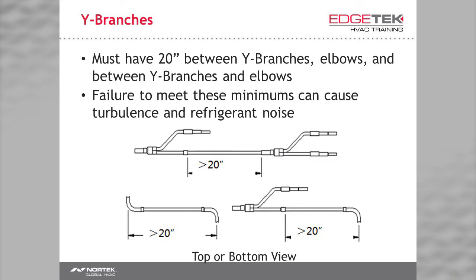The next rule is the minimum distance between Y branches, elbows and Y branches. Let's call this the 20-inch rule. As long as you have 20 inches between each, you'll maintain proper flow and it won't be noisy. Would you say piping is important? I say it, so you should too. The quickest way for a beautiful system to become scrap is poor piping.